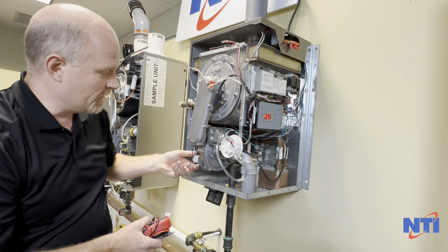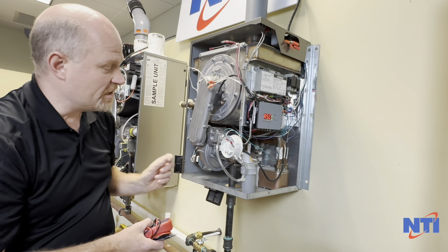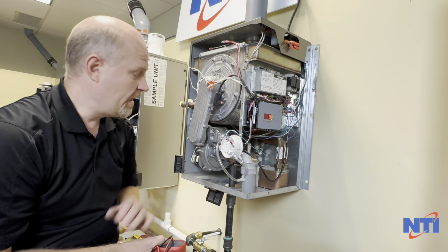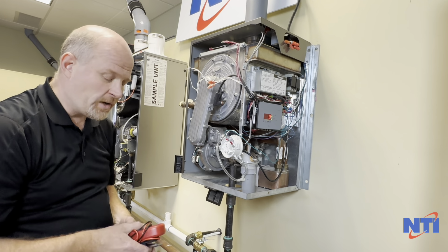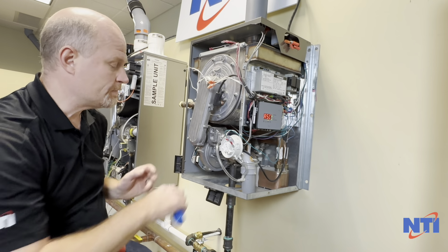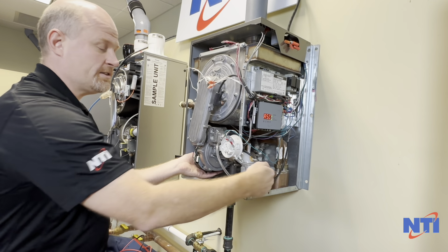And another way to do this is just to disconnect the low voltage. And if you disconnect the low voltage and all of a sudden the controller goes to an ASO code, that means your fan was still running and it's not supposed to be. So if your fan remains running, so you felt it, you can feel a slight vibration, the next step is going to be to find the low voltage wires. They're down in the bottom here.